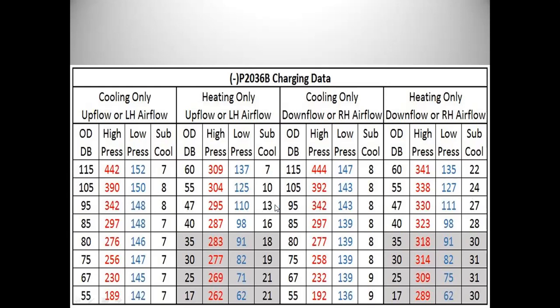Now, ideally, you want to undershoot these by at least 3, if not 5 degrees, to give you some leeway here, to not be anywhere near overcharged. So in this case, if you're at a subcool of 13, I would shoot for a 10. And that's going to give you a nice safe spot there. If you're in a downflow, same chart, you're calling for 27 degrees. So at that point, I would probably shoot for like a 22. You're going to be 5 degrees under, and that's going to give you a nice safe spot in between without overcharging it. So about 8 to 10% less in that vicinity.